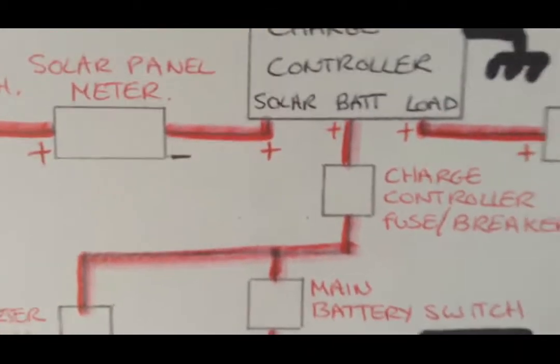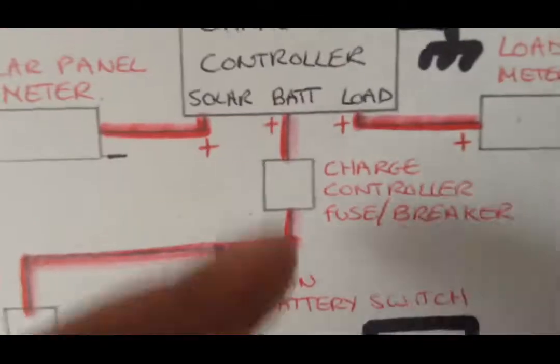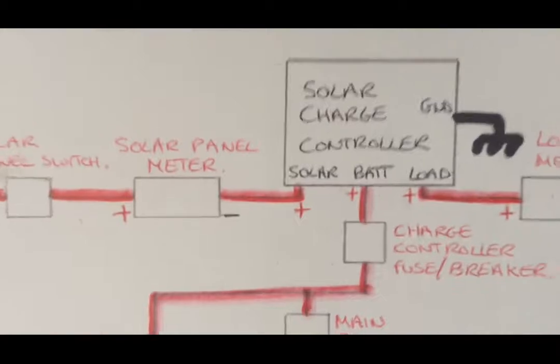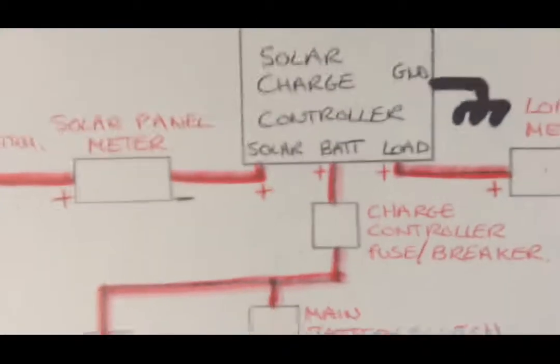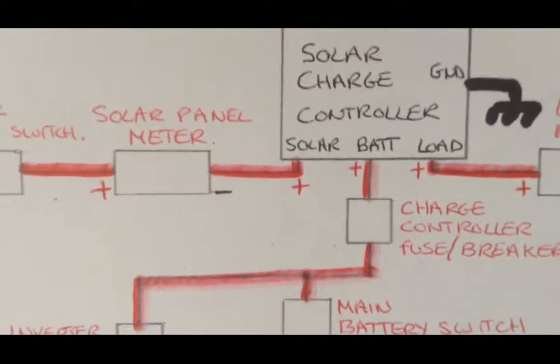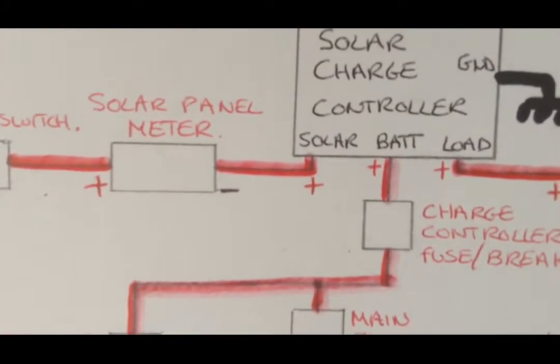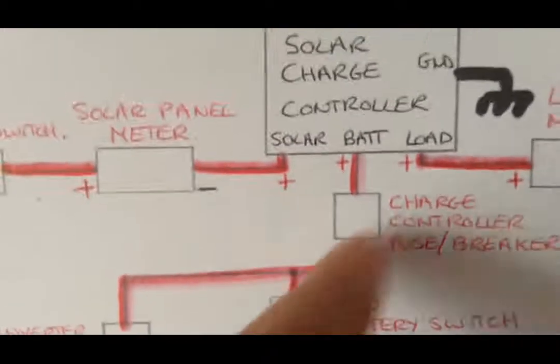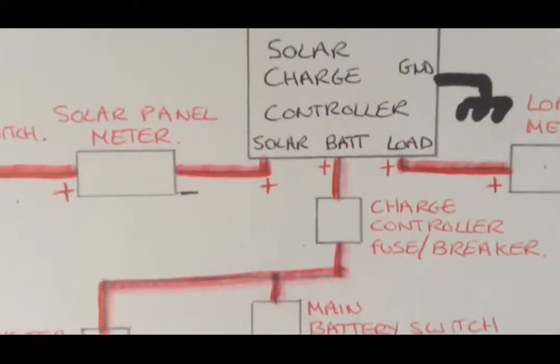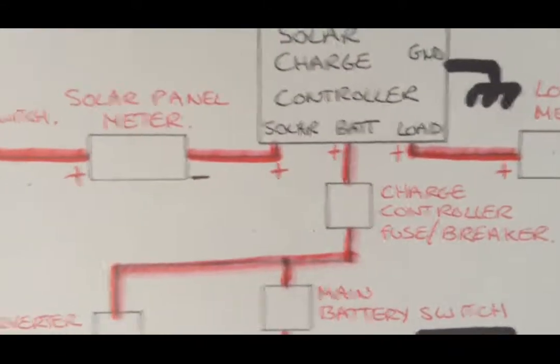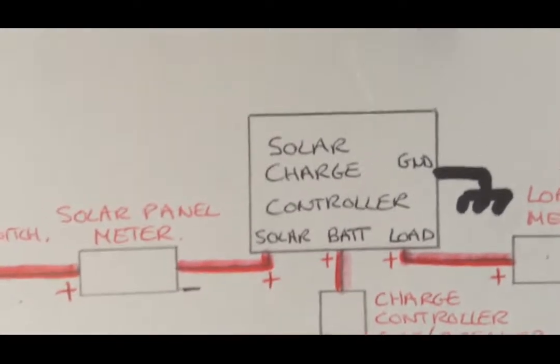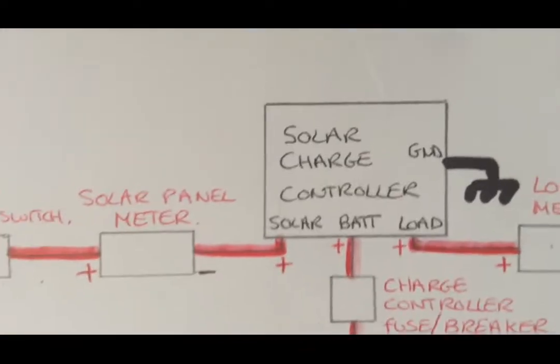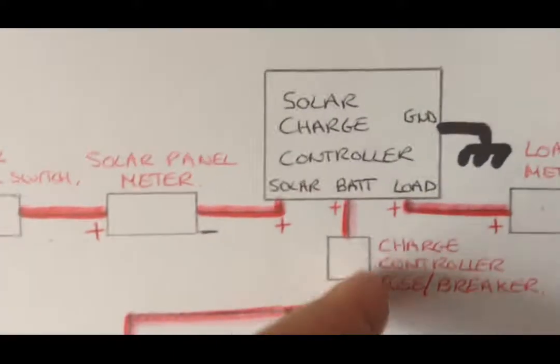The fuse or breaker that you use must match the charge controller. So if you have a 20 amp charge controller, for example, then you should use a 20 amp fuse or breaker. So that's how that works. Also, the fuse protects the charge controller. If there's a short in one of your load devices, then it will blow the fuse or trip the breaker. Although most charge controllers do have protection built in, it's better not to rely on it, so better use a fuse or breaker.